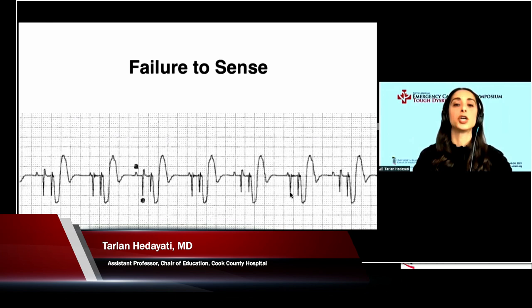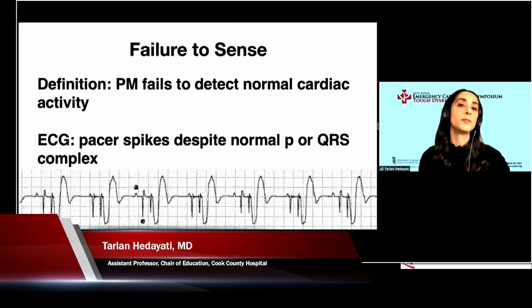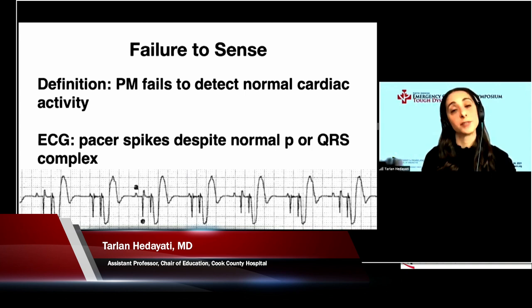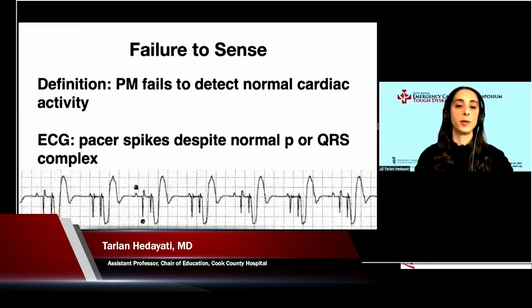So this is an example of failure to sense for the atrial lead. When you look at the EKG, the pacer spikes are going to be present in spite of a normal P or QRS complex, and that's your clue that you're dealing with failure to sense. Lots of different things can cause failure to sense, whether maybe the lead is in the wrong place or the pacemaker itself, its sensory function needs to be manipulated or reprogrammed. But this is a great example of failure to sense for the atrial lead.